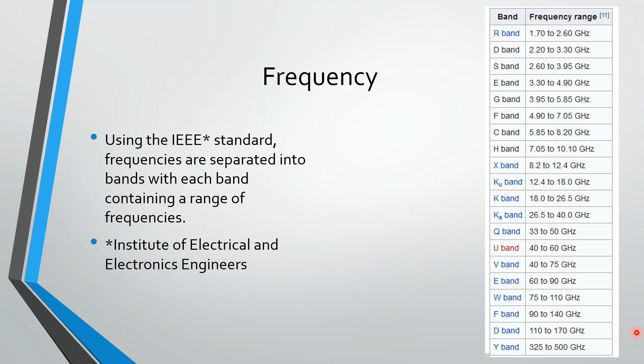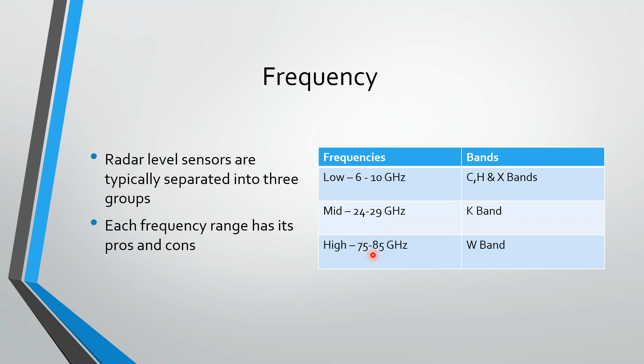So we basically have 3 groups that we separate our non-contact radar devices into: the low frequency range, the mid frequency, and the high frequency. Low, 6 to 10 gigahertz, operates within the C, H and X bands. 24 to 29 operates in the K band. 75 to 85 operates in the W band.